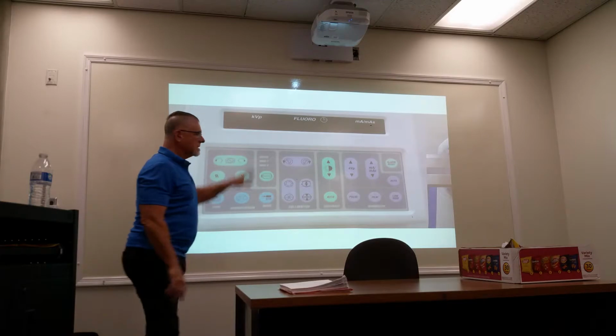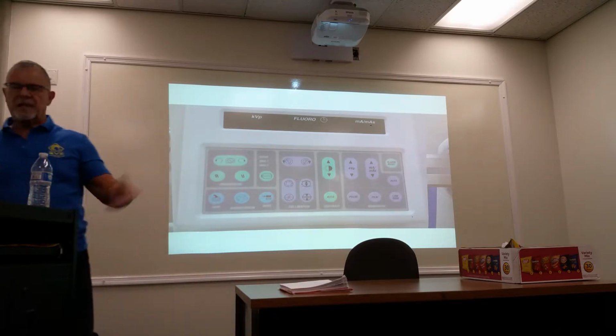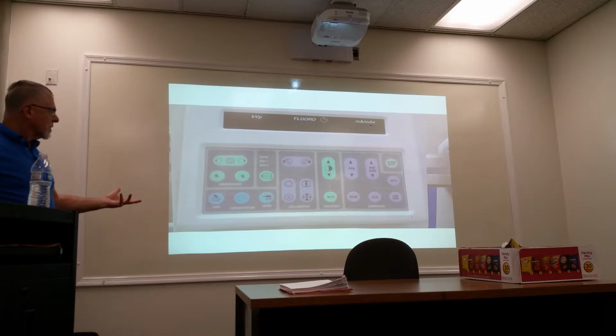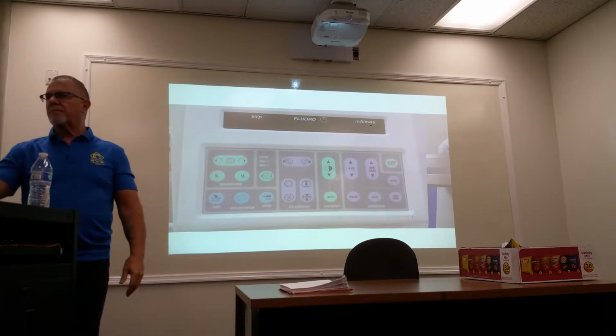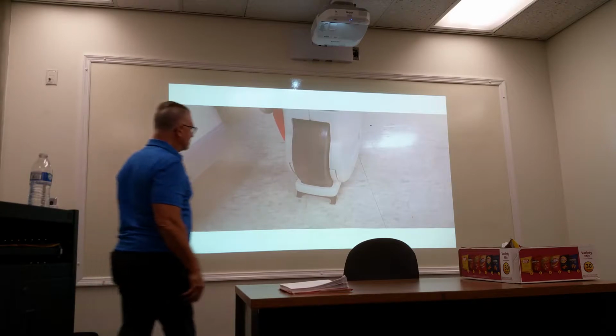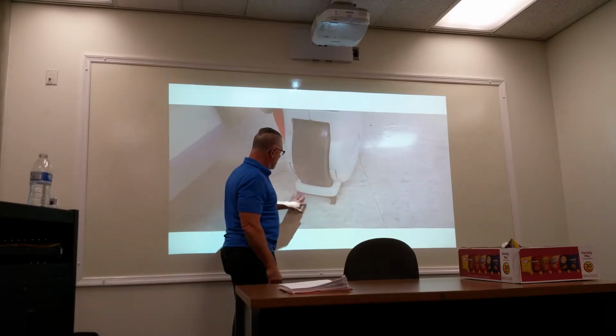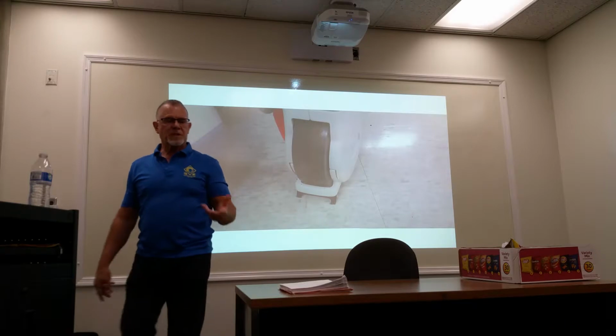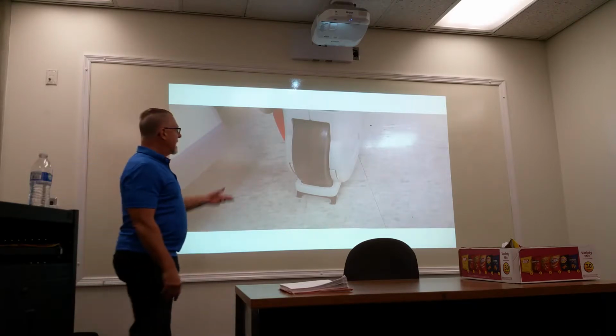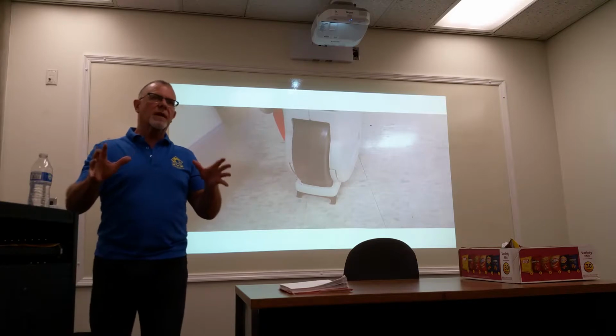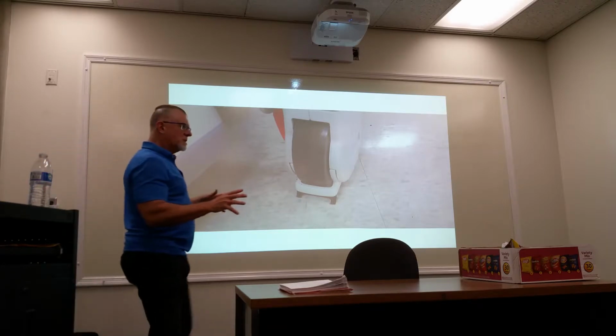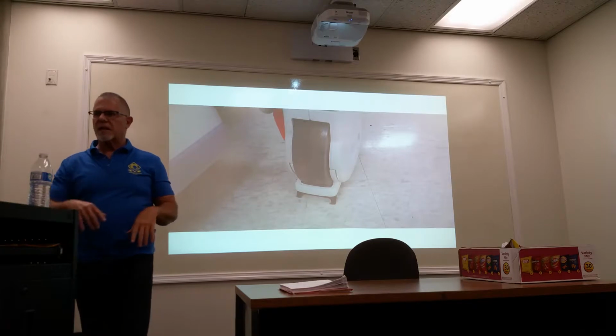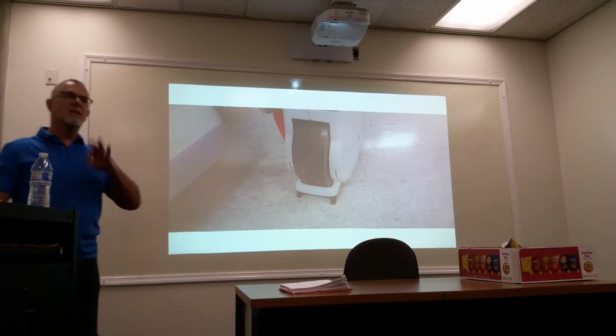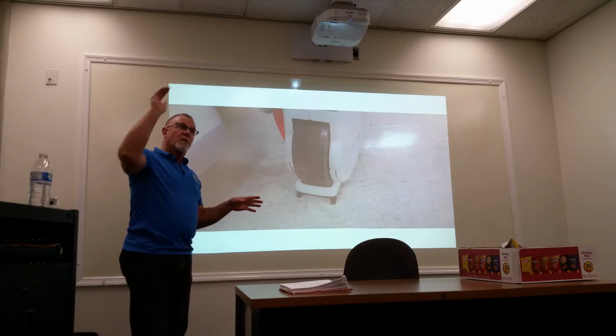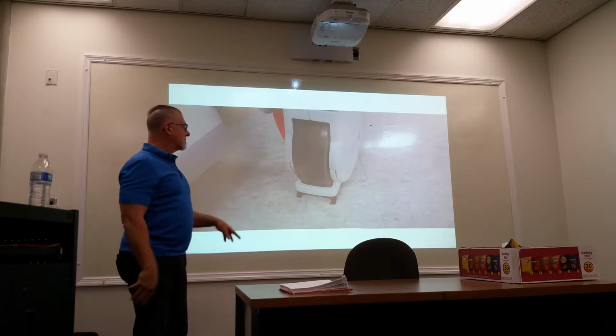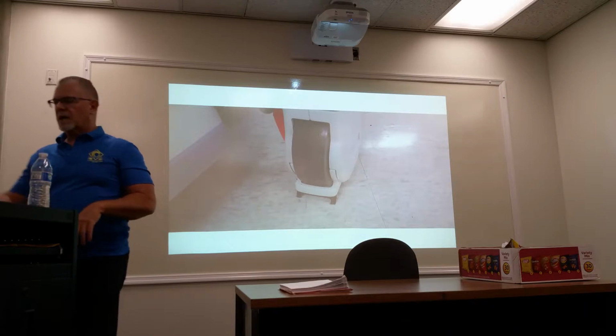This is probably one of the easiest systems to understand. I think just about anybody can take this into a room and figure out pretty much what they need to do and how to set what. This is your wheel lock. This is the side that basically hits the floor. Once these are locked in place, you want to make sure they're locked really well, and that the unit is pretty much where it needs to be. All the rest of the controls are up above, and you can change orientation, but these are all manual locks. That's different from a regular fluoroscopic unit because those are fixed to the floor. These have manual locks.